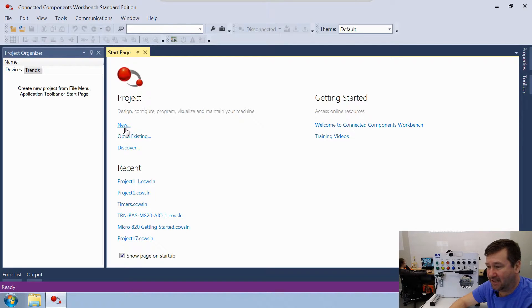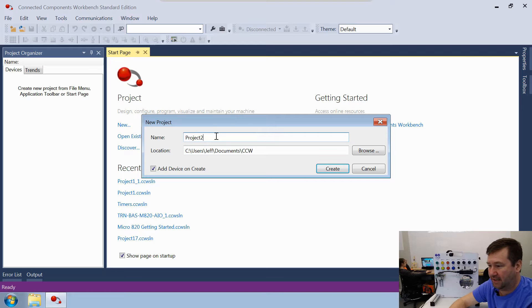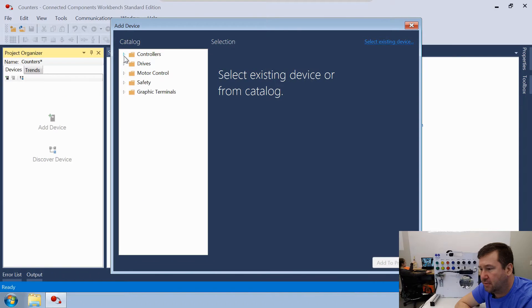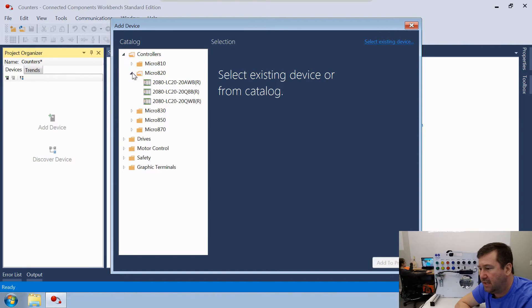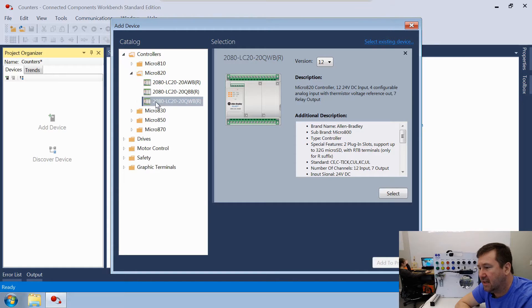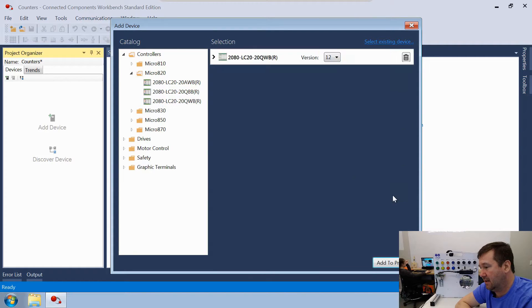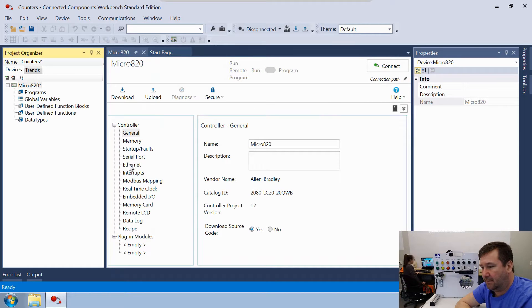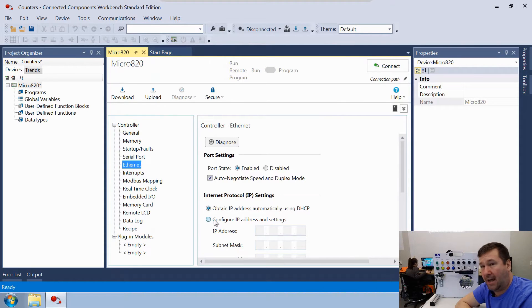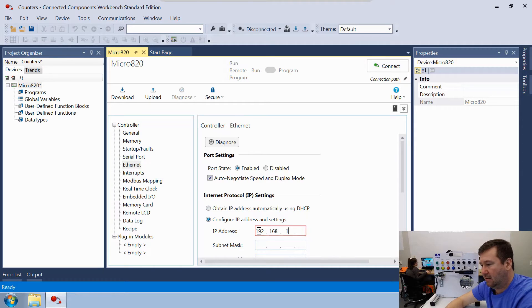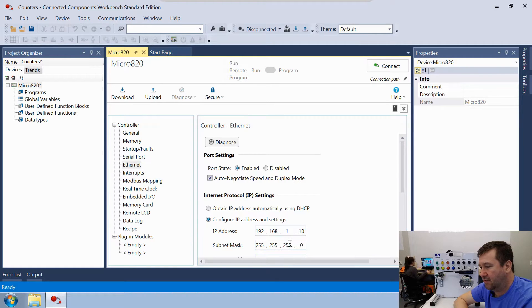We're going to start with a new project in Connected Components Workbench and call it 'counters'. Then we go to controllers and the Micro 820, selecting the 2080-LC20-20QWB using version 12 — I highly recommend at least version 12 since we're using that logics theme. We'll add it to the project and set up the Ethernet configuration, configuring the IP address to 192.168.1.10 with a subnet of 255.255.255.0.